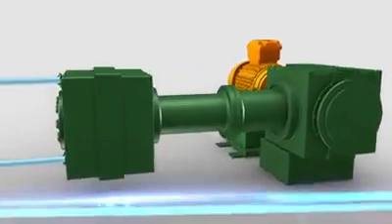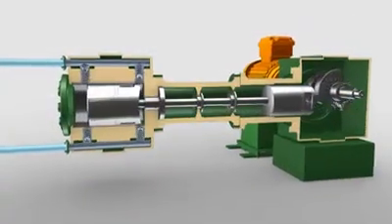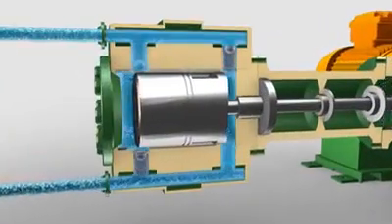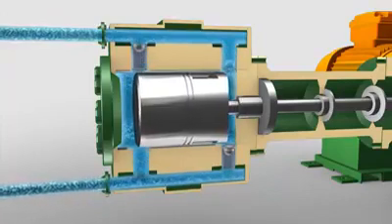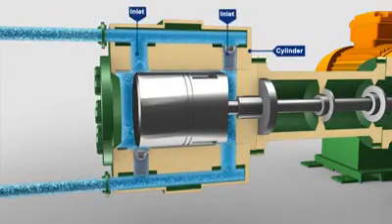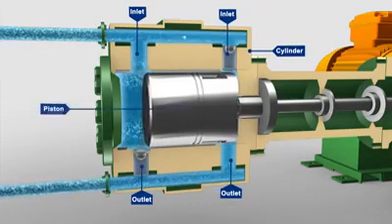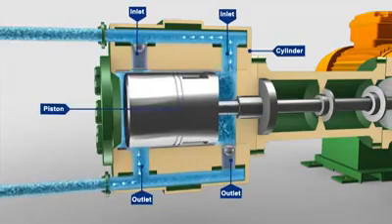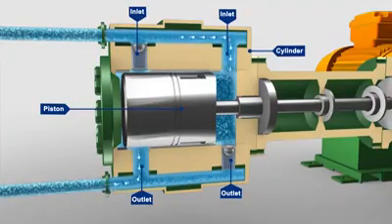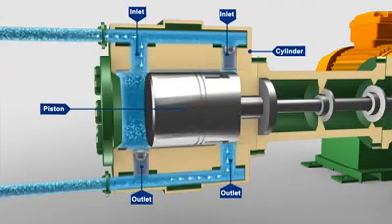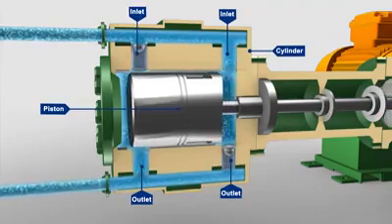This type of pump operates in exactly the same way as the single acting with respect to its action. The difference is that the cylinder has inlet and outlet ports at each end of the cylinder. As the piston moves forward, liquid is being drawn into the cylinder at the back end while liquid is being discharged at the front end. When the piston direction is reversed, the sequence is reversed.